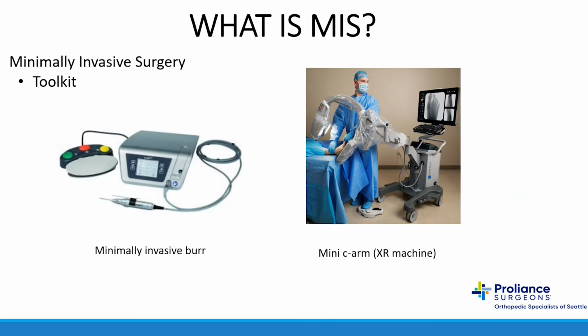It's based on having a high torque and low velocity so that it doesn't create too much thermal energy, so that there's not a bunch of thermal transfer or injury to soft tissue structures like skin and tendons and blood vessels when I'm operating. But the high torque aspect of it lets me have a lot of power and do even bony work, and I'll talk a little bit more about that.